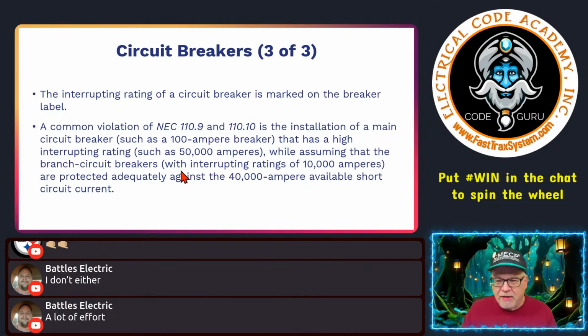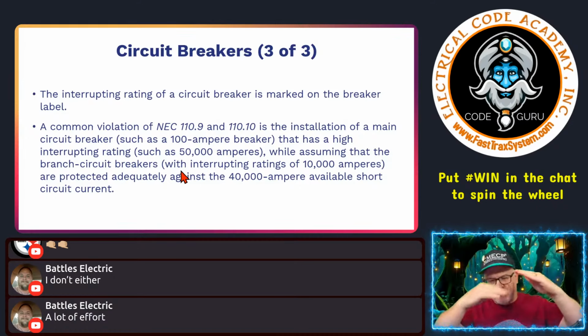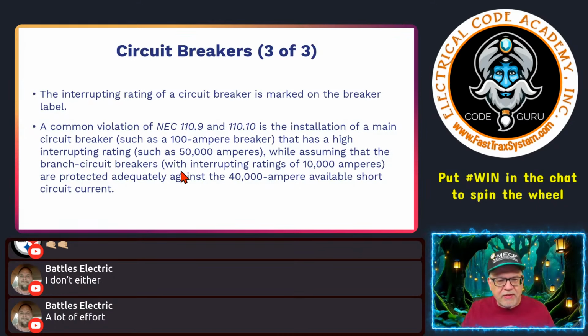Common misconception. If I have a main breaker that is rated as a 100 amp breaker, or it's a remote distribution panel, right? And it is rated for 50,000 amps, right? And it's high rated, but the breakers that I put in it are only rated for 10,000, it means I didn't look at the system properly. I didn't design it properly, unless these breakers are series rated for a certain application and how they're installed in a panel, so it's kind of a structured hierarchy.